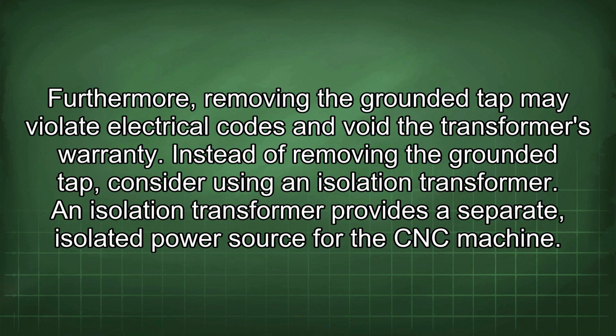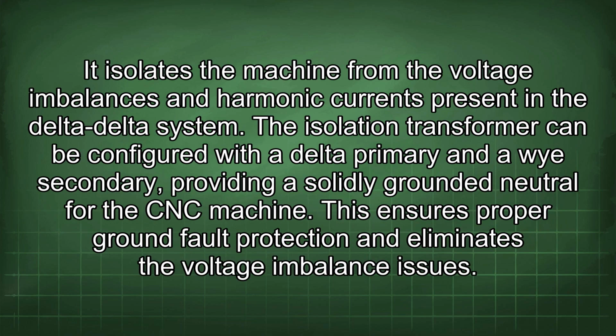Instead of removing the grounded tap, consider using an isolation transformer. An isolation transformer provides a separate, isolated power source for the CNC machine. It isolates the machine from the voltage imbalances and harmonic currents present in a delta-delta system. The isolation transformer can be configured with a delta primary and a Y secondary, providing a solidly grounded neutral for the CNC machine. This ensures proper ground fault protection and eliminates the voltage imbalance issues.